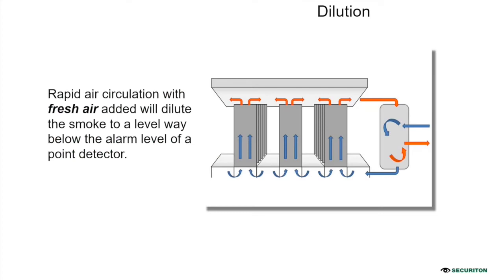This picture shows the air circulation of HVAC. Rapid air circulation with fresh air added will dilute the smoke to a level way below the alarm level of a point detector. So it is almost impossible to detect smoke in this kind of environment if you are using the normal smoke detection system.